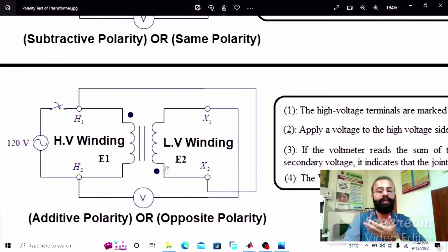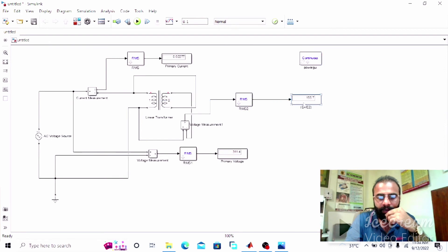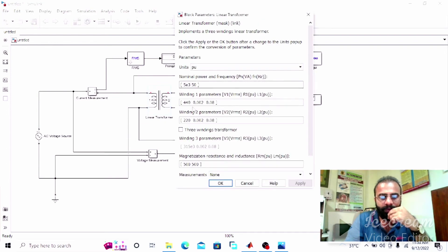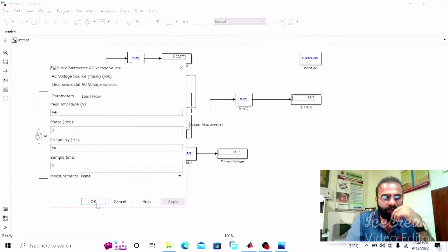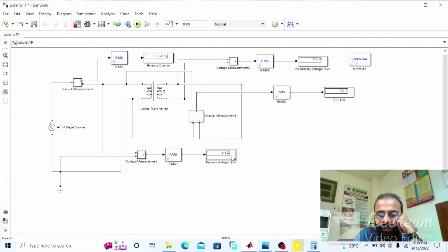We have connected H1 with X2 and X1 with H2, with the voltmeter in between, which will give us the sum of the induced EMFs E1 plus E2. Now verify the results. The parameters remain the same: 440 volts for the HV winding, 220 volts for the LV winding, with 440 volts applied. The voltmeter connected in parallel across the secondary winding will give us the E2 value.